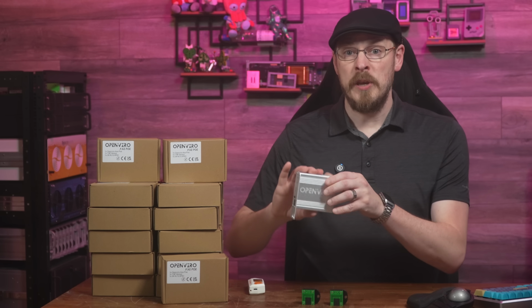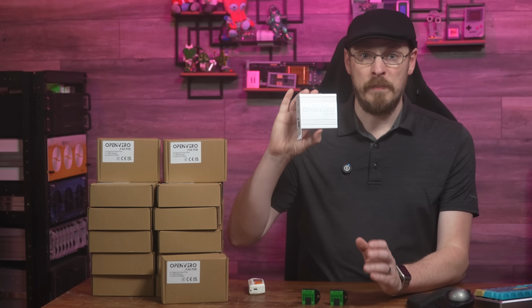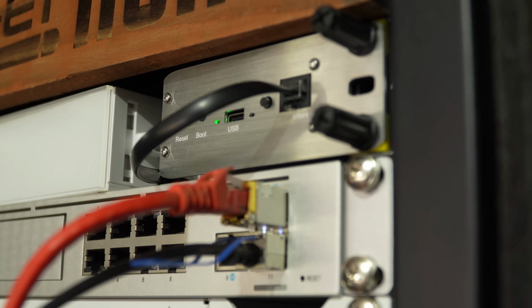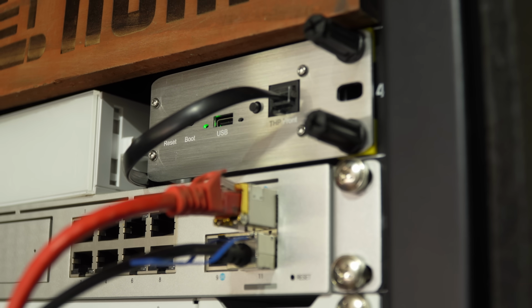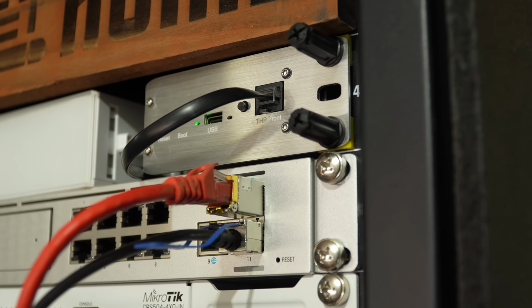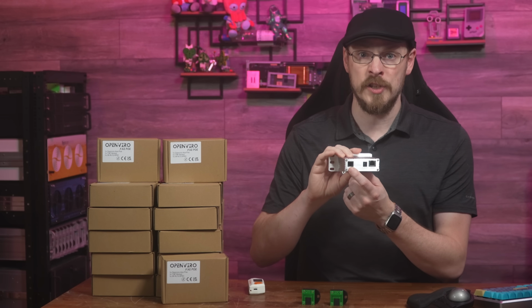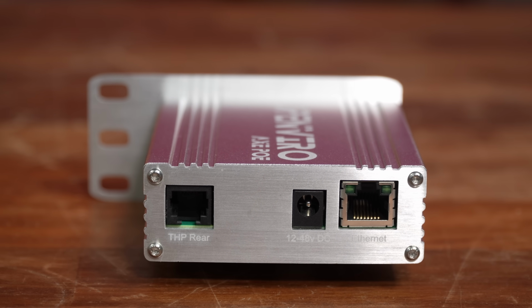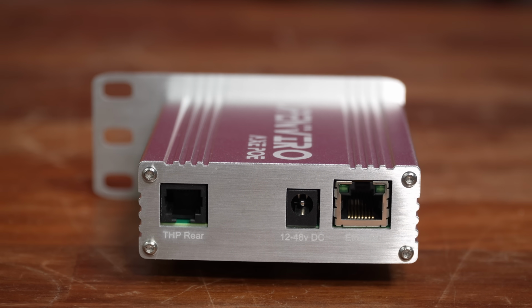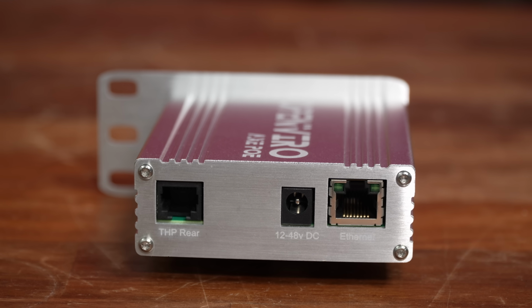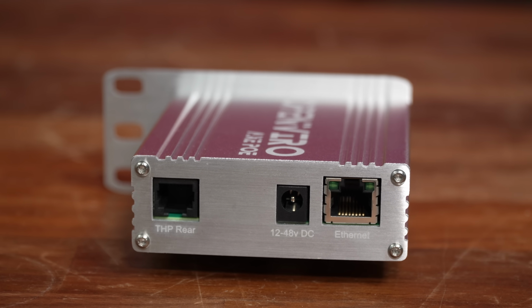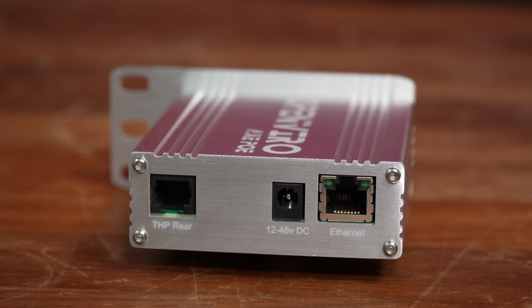The Openviro Axe PoE controller is a Class 1 active PoE device and can be powered by most PoE switches or injectors. If you don't have a PoE switch, there's also a 5.5mm barrel jack around the rear, supporting 12 to 48 volt DC power, or you can use the USB-C port on the front of the unit. The USB-C port also doubles as the serial port and is how you access the configuration for the controller.